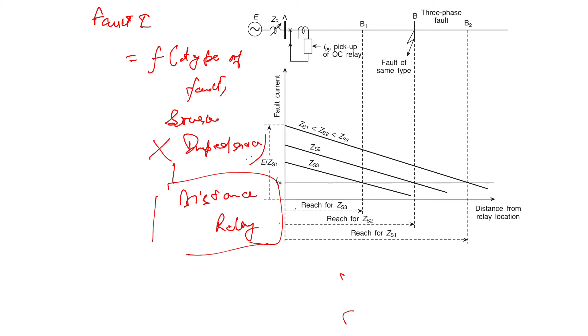Now let us consider the transmission line AB as shown in the figure. Let us assume that there is a source only at the end A, that is, a singly fed system, and we wish to generate a zone of protection which extends from A to B. Now assume that the proposed relay is located at the end A, where the current and the voltage are available through the CT and the PT, whose ratios we assume to be 1:1 for simplicity. Now the reach of the distance relay is made equal to Z set.